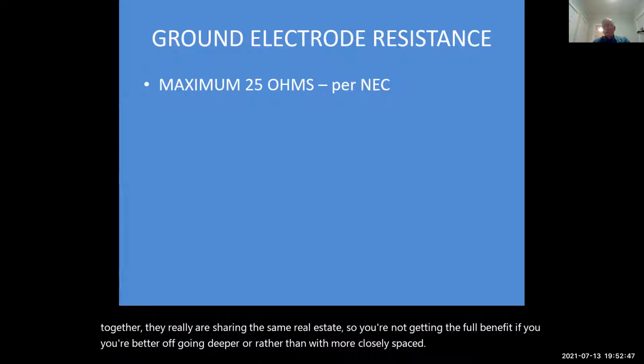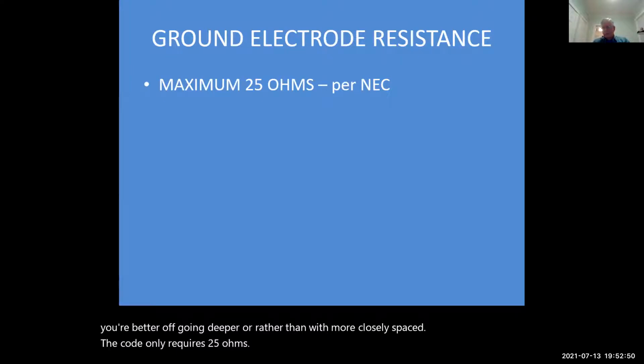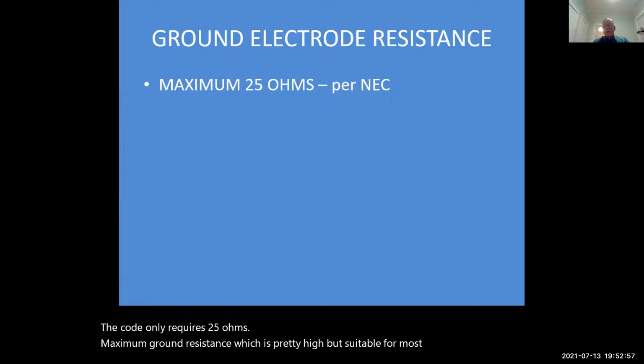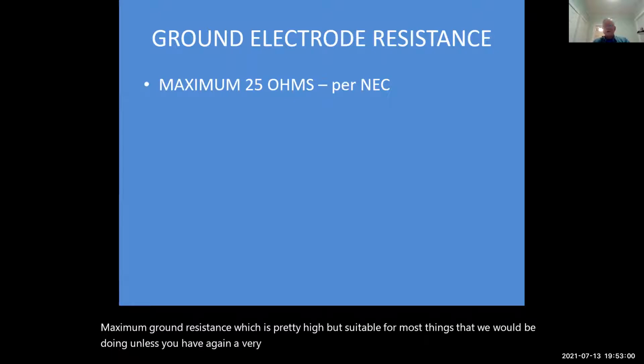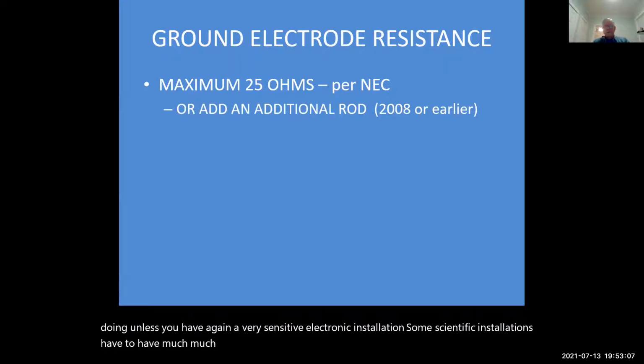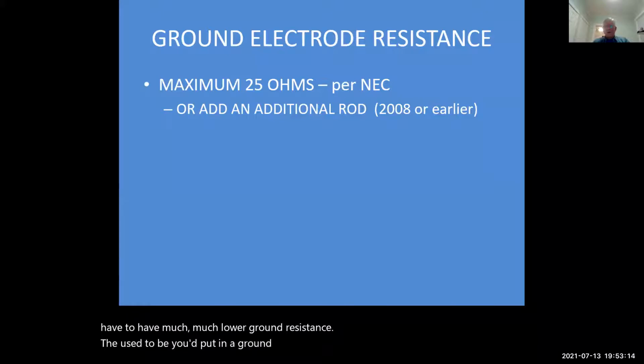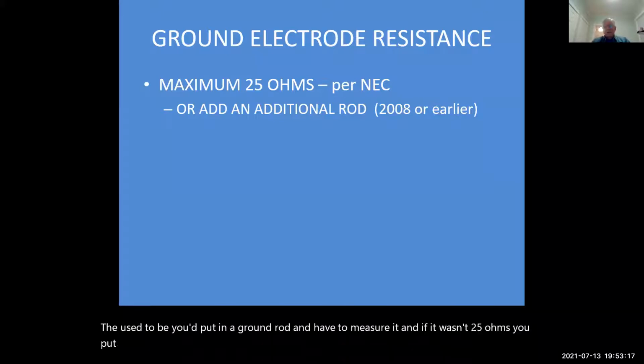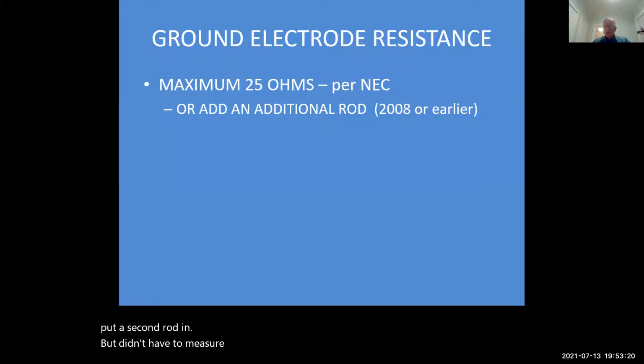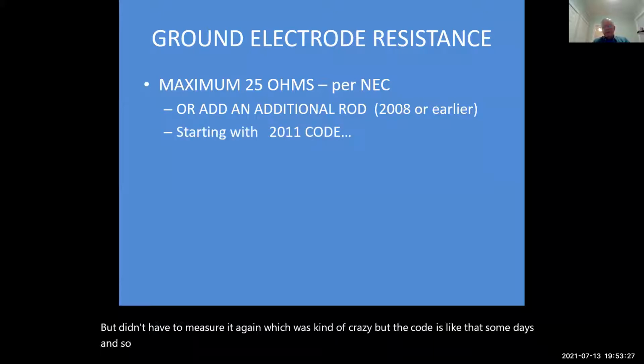The code only requires 25 ohms maximum ground resistance, which is pretty high, but suitable for most things that we would be doing unless you have, again, a very sensitive electronic installation. Some scientific installations have to have much lower ground resistance. It used to be you'd put in a ground rod and have to measure it, and if it wasn't 25 ohms, you put a second rod in, but didn't have to measure it again, which was kind of crazy, but the code is like that some days. And so now, after 2011, they said we'll just put in 2 ground rods because it's cheaper than having to bring some guy out to do any testing.